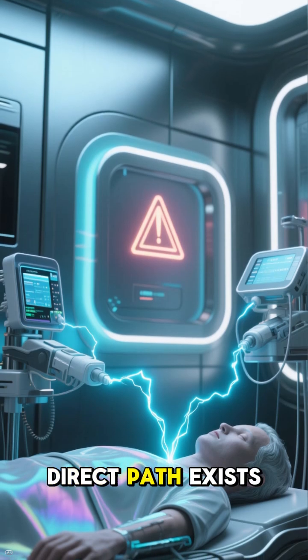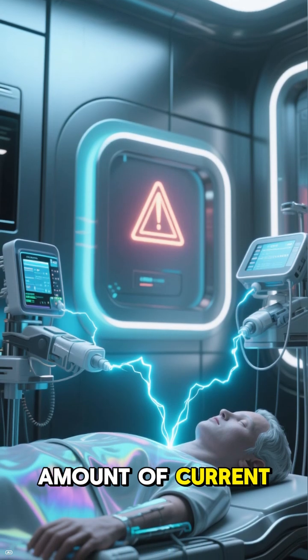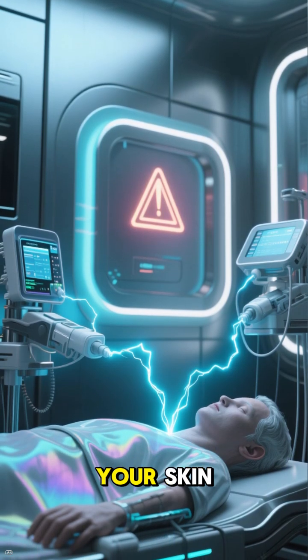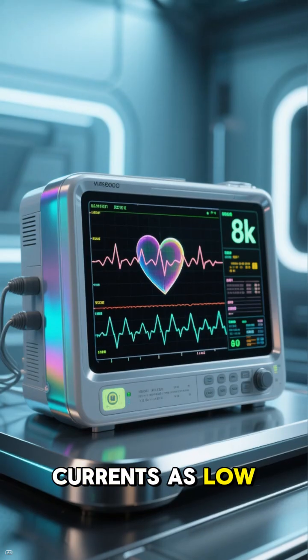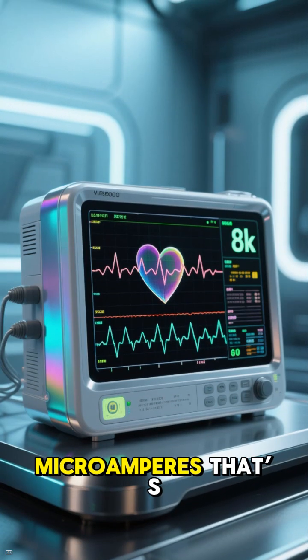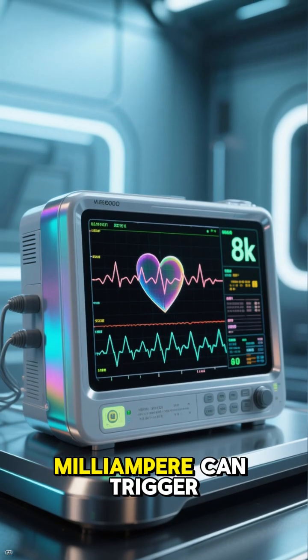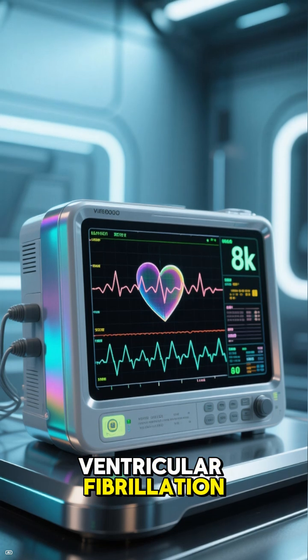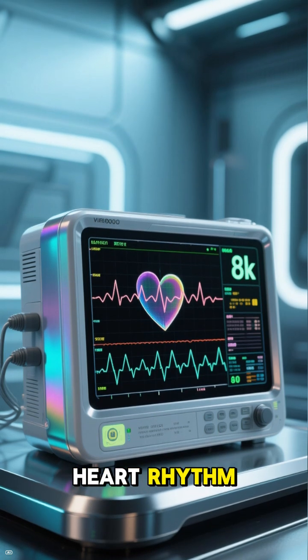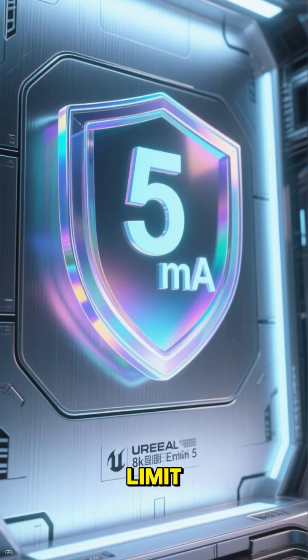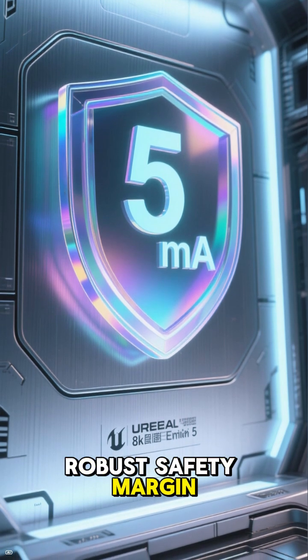When such a direct path exists, even a tiny amount of current, far too small to feel on your skin, can be lethal. Currents as low as 10 to 20 microamperes, that's thousandths of a milliampere, can trigger ventricular fibrillation, a chaotic and life-threatening heart rhythm. The 5 milliampere limit acts as a robust safety margin.